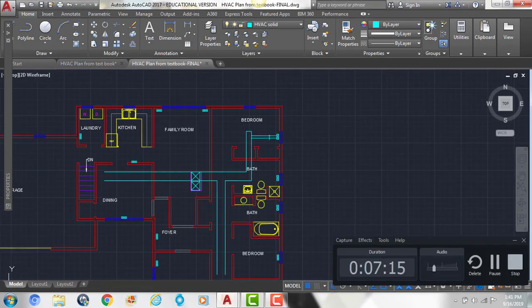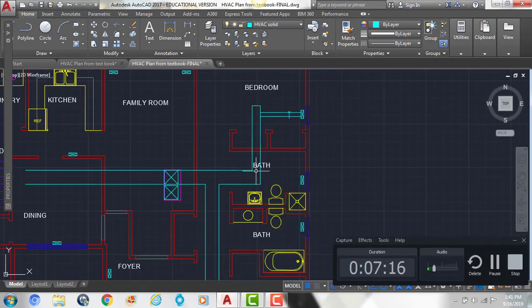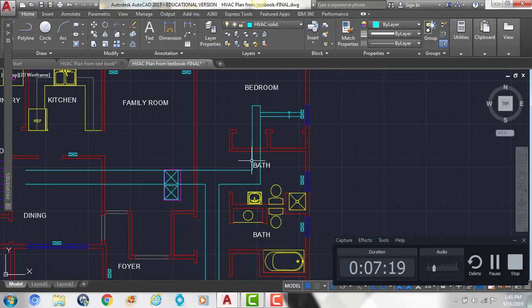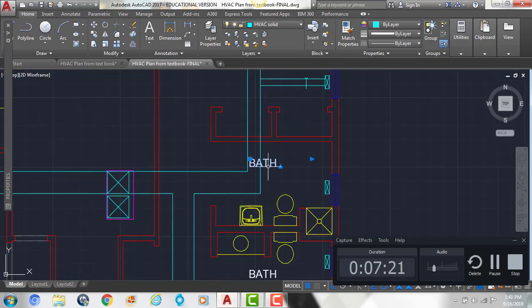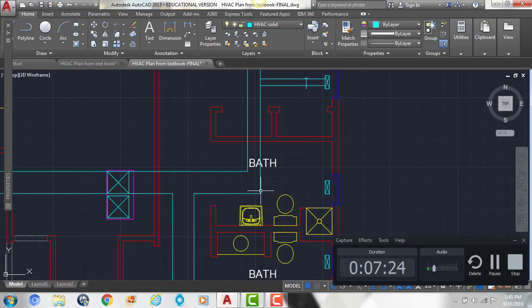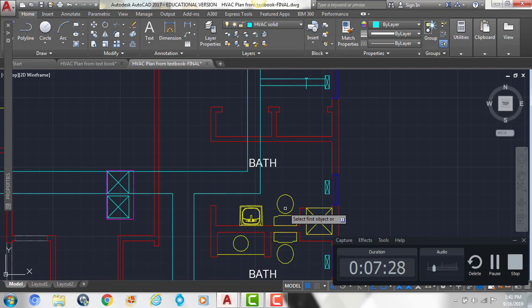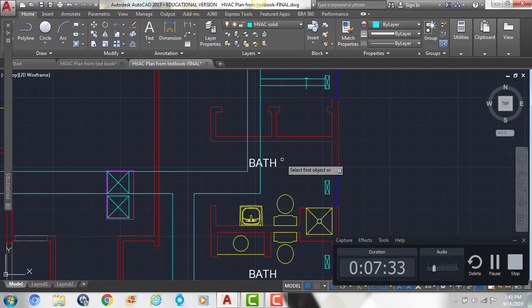And now we're going to use the fillet command to give us our curve here on this duct. So what we're going to do, the radius here is going to be 6 inches and 3 inches on this one. So if I type F, enter, and then R, enter for radius, put in 6, enter, click the two lines.